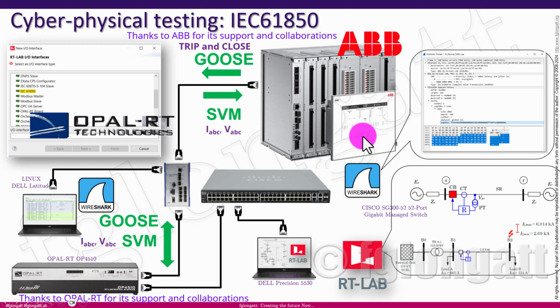Assuming there is a fault condition, the relay will generate a trip signal. For this, we use the very important GOOSE signal, one of the services coming from IEC 61850. This GOOSE signal goes back to the digital real-time simulator, and when it arrives, it represents the signal ordering the circuit breaker to open in order to stop the fault.